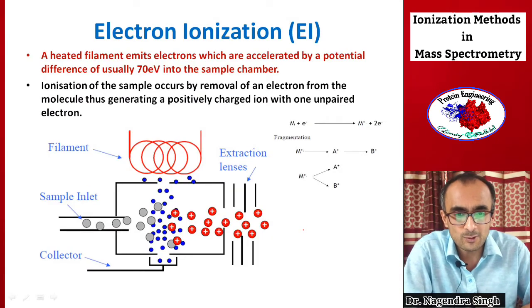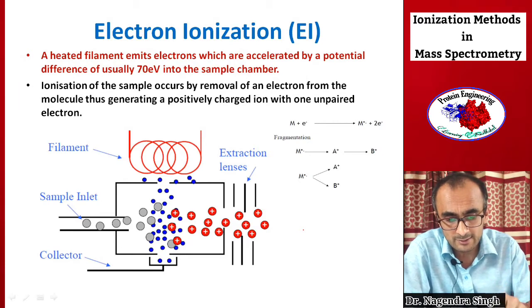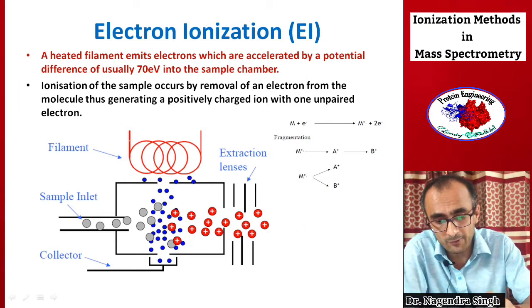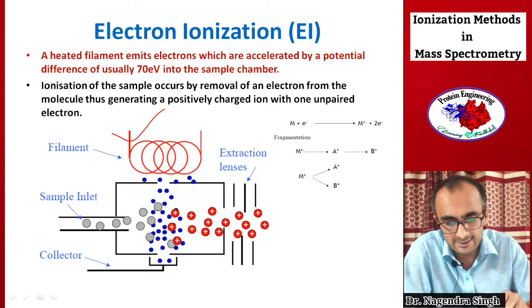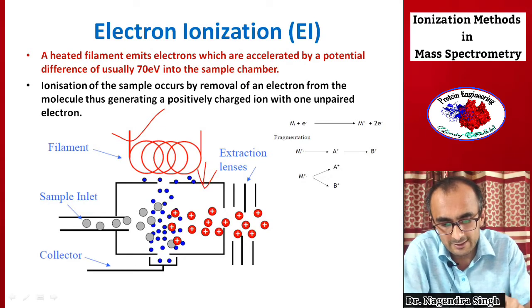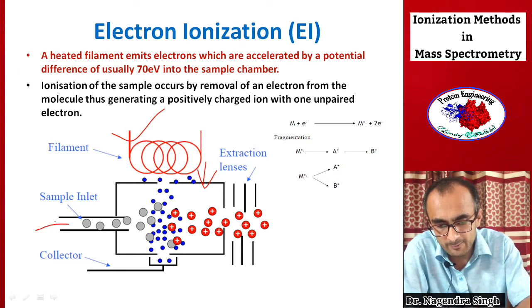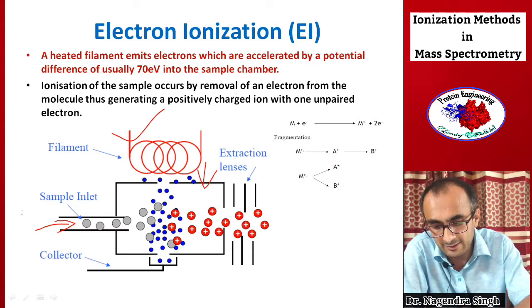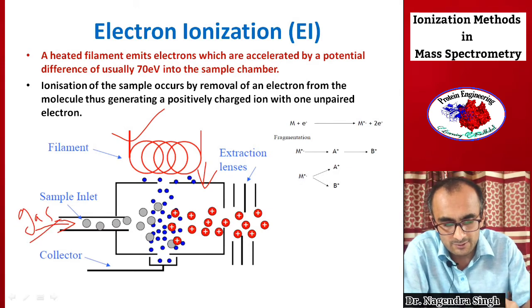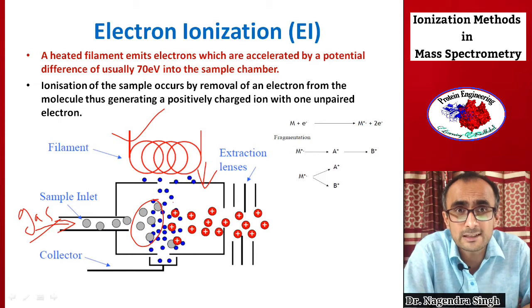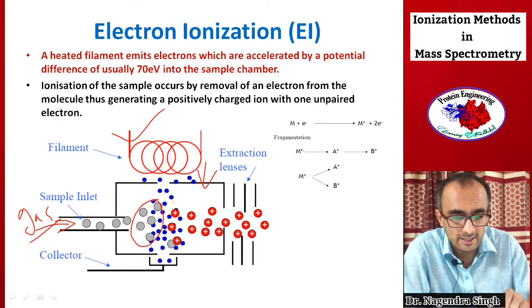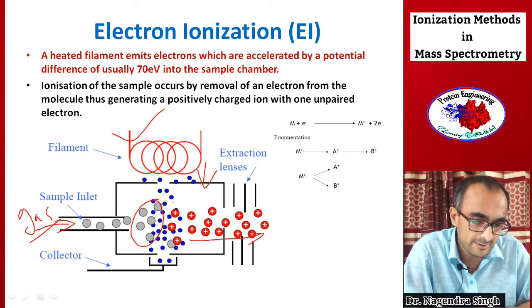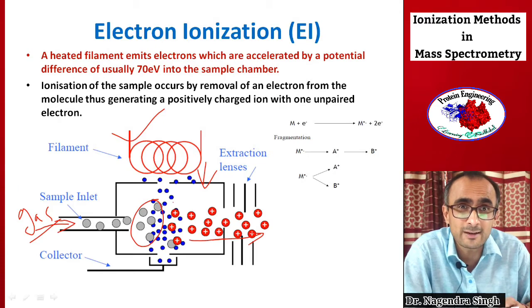In the electron impact ionization chamber, there is a filament that is electrically heated. This filament liberates electrons. The sample analyte enters in the gaseous or vapor state, and when the electrons collide with the sample, they knock off electrons from it. As a result, molecular cations are formed, and these positively charged ions are then accelerated into the analyzer and detected.